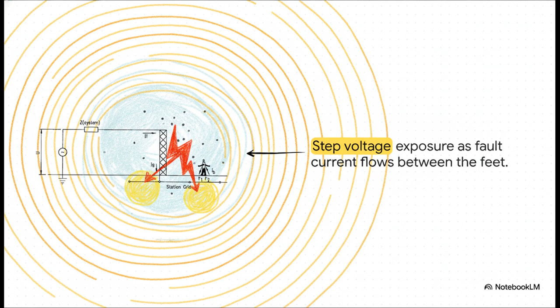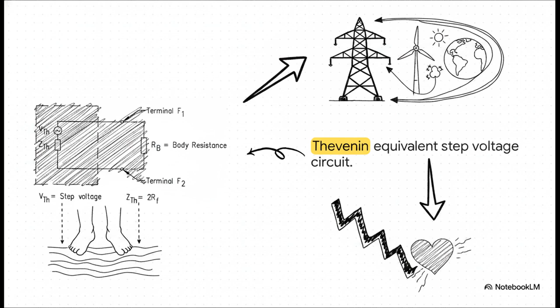Once again, the IEEE standard models this as a Thevenin equivalent circuit. By factoring in the human body resistance between those 2 feet and calculating the Thevenin impedance of the earth beneath them, engineers can pinpoint the exact maximum step potential. They calculate this as a percentage of the total ground potential rise to definitively ensure it stays well below the threshold that would cause a human heart to enter fibrillation.